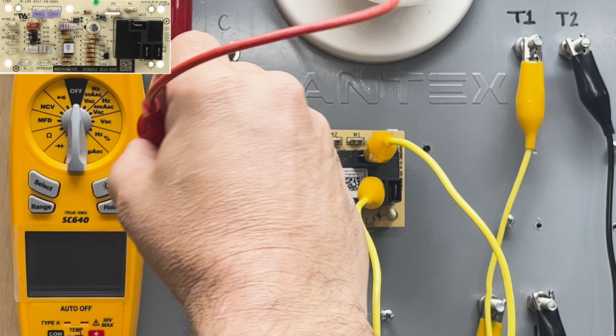So we're already putting 24 volts onto the board. We just need to give it a path back to the transformer. We're going to skip past the second terminal here, which is R, and come down to XFMR-C. I'm going to connect to this terminal and run it back up, pushing my alligator clip with a little insulation around it - I know that's blocking some view, but I don't want to short 24 volts on my board and blow my fuse.